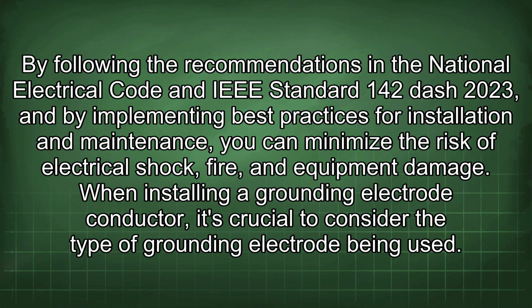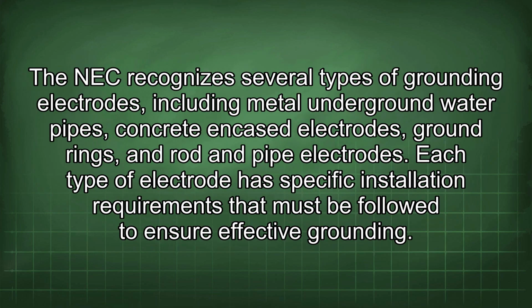When installing a grounding electrode conductor, it's crucial to consider the type of grounding electrode being used. The NEC recognizes several types of grounding electrodes, including metal underground water pipes, concrete encased electrodes, ground rings, and rod and pipe electrodes.